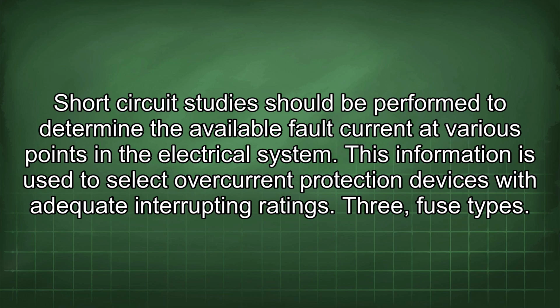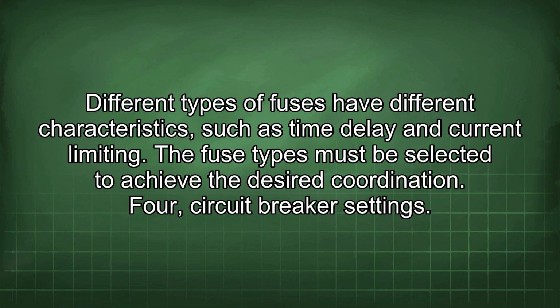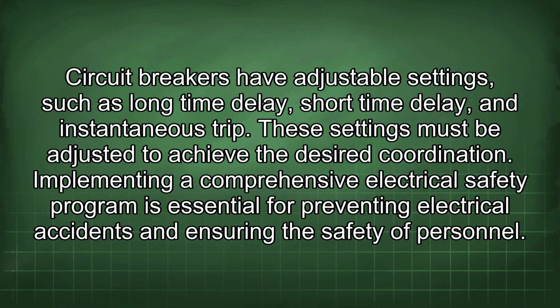3. Fuse types. Different types of fuses have different characteristics such as time delay and current limiting. The fuse types must be selected to achieve the desired coordination. 4. Circuit breaker settings. Circuit breakers have adjustable settings such as long time delay, short time delay, and instantaneous trip. These settings must be adjusted to achieve the desired coordination.